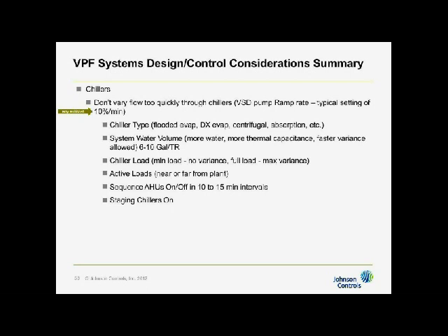Most HVAC systems don't need more than 5. Most of the buildings that have been done by the folks that are going to give you the next webinar usually set them around 5 because they just don't need faster than 5. The building doesn't call for it. Only in special circumstances where you got some big load that drops off, like a process load or something. But with normal HVAC, 5's plenty, so we usually set them to 10.